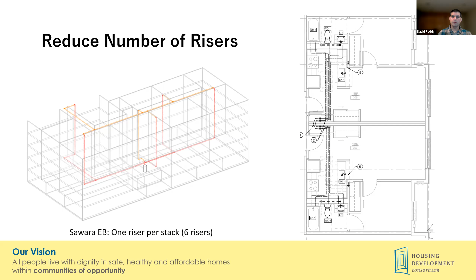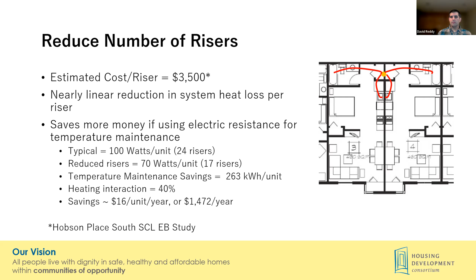So by limiting risers, you can save materials, like the estimated cost per riser that we had from one study was $3,500. And then you save energy too, because the risers make up the majority of the pipe length in the building. The pipe length is pretty directly proportional to the energy lost. And by reducing risers, for Hobson Place, we estimated going from 24 to 17 risers and saving roughly $16 per unit per year. And that's even after accounting for the fact that Alistair mentioned that heat in the riser does dissipate to the building. It offsets some of the heating load. About 40% is what you could use as an estimate of that effect. But it still saves a fair amount of money over time.